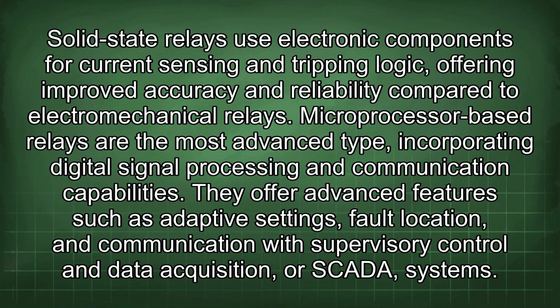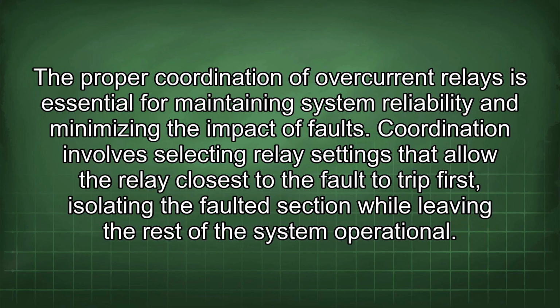Solid-state relays use electronic components for current sensing and tripping logic, offering improved accuracy and reliability compared to electromechanical relays. Microprocessor-based relays are the most advanced type, incorporating digital signal processing and communication capabilities. They offer advanced features such as adaptive settings, fault location, and communication with supervisory control and data acquisition, or SCADA, systems. The proper coordination of overcurrent relays is essential for maintaining system reliability and minimizing the impact of faults.